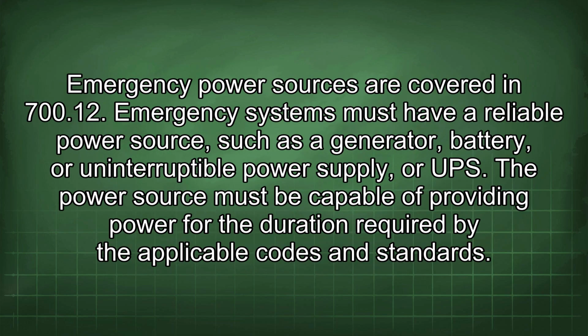Emergency power sources are covered in 700.12. Emergency systems must have a reliable power source, such as a generator, battery, or uninterruptible power supply, or UPS. The power source must be capable of providing power for the duration required by the applicable codes and standards.